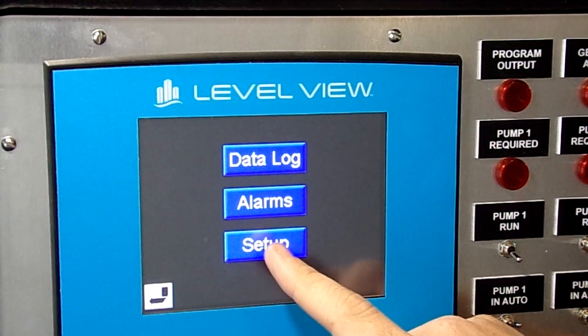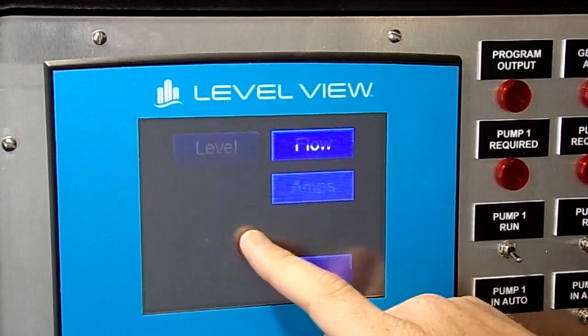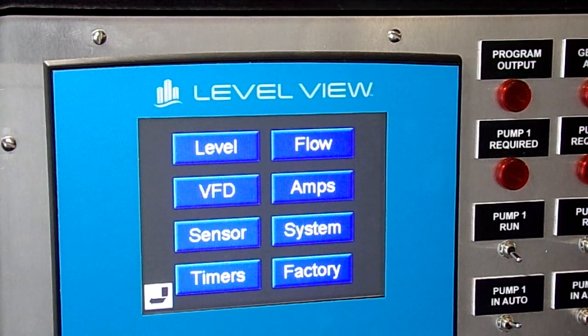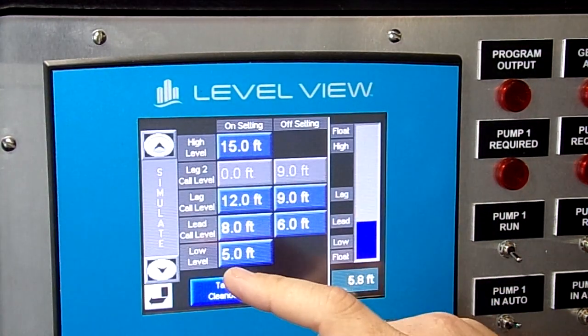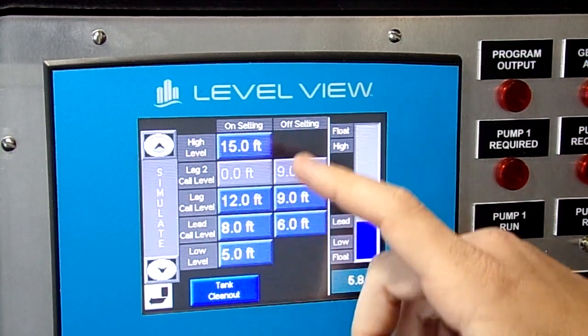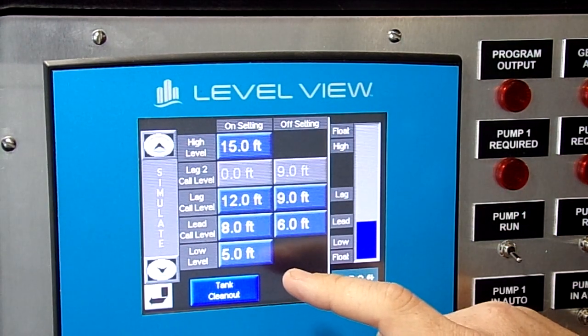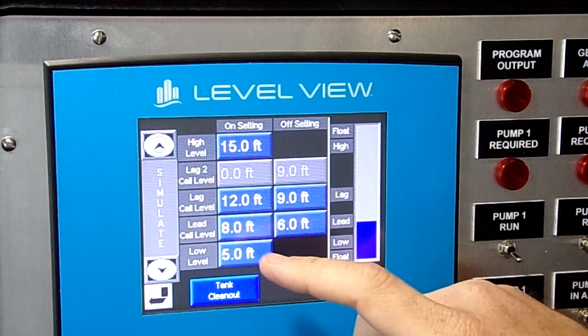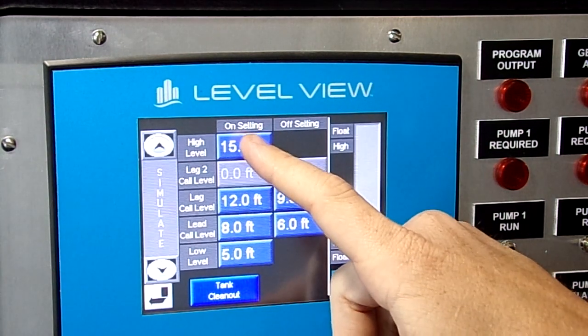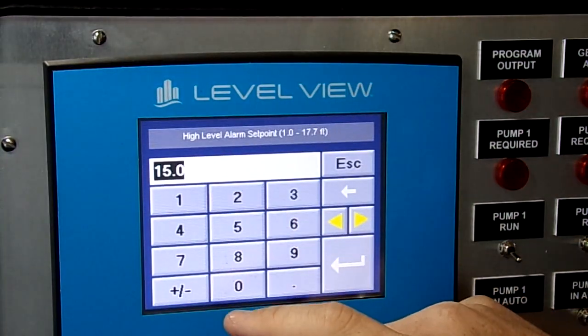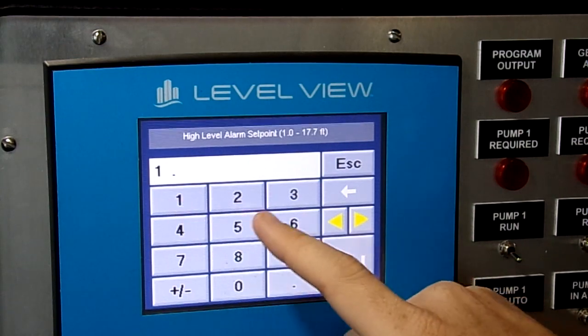When we get into the setup screen, it will give us all of our programming features that we have access to. If we do our level first, you will see that we have a range that we can set our transducer for a low, lead, lag, and high water. These can simply be changed by clicking the button and clicking what we want to change these to.